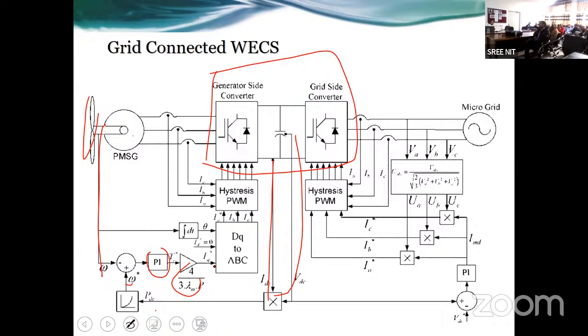So the rotor flux is already fixed. You don't need to control it. So ID you can keep 0. IQ is there just to control the torque on the machine according to the power. So ID 0, IQ is there, and theta is taken from speed itself. By integrating it, you are getting the theta. So dq to abc transformation. So IA, IB, IC reference is coming, and actual IA, IB, IC, then PWM.